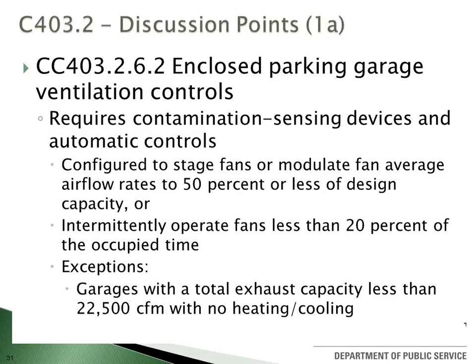There are requirements for modulating and variable speed control of fans, actually operating on sensing devices. It's like demand-controlled ventilation in conference rooms now, where you can sense too much CO2 from occupants - same thing in parking garages. Let's have sensing devices operate fans rather than running 8,760 hours a year.